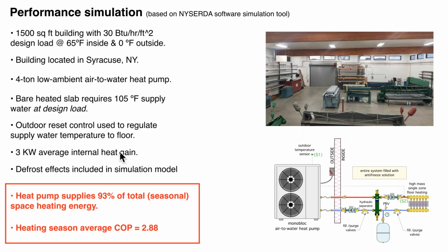And I was impressed. I think that's a very respectable number. It's starting to approach numbers for geothermal heat pumps. It may not be quite as good, but especially in a retrofit, it's certainly much lower cost, and even in new construction, definitely lower cost. In an unsubsidized market, the return on investment is definitely better on the air-to-water than it would be on a geothermal. So it shows you that you're going to get respectable performance in this type of system in a relatively cold winter climate.